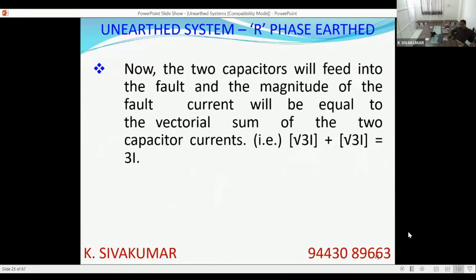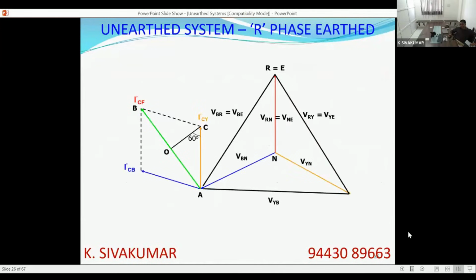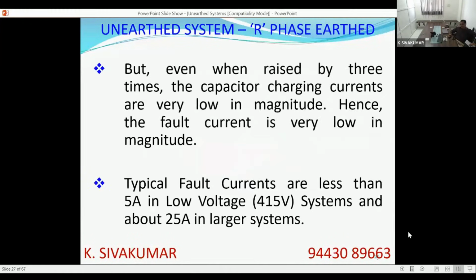Now, the two capacitors will discharge into the fault, will feed into the fault, and the magnitude of the fault current will be equal to the vector sum of the phase currents, that is √3I and √3I, which will become 3I. Like this, in this triangle, you can do the trigonometrical equation. The vector AB will be equal to 3I actually. Now, you need not worry, even when raised by 3 times, the capacitor currents are still very low in magnitude. So the fault current is very low.